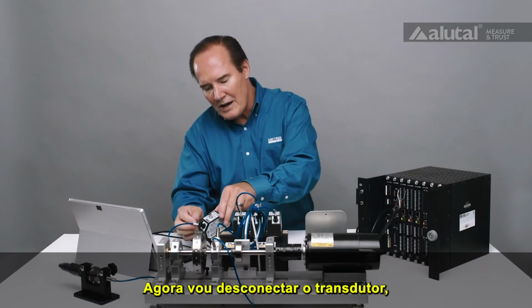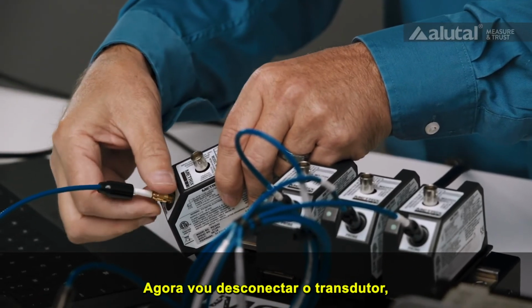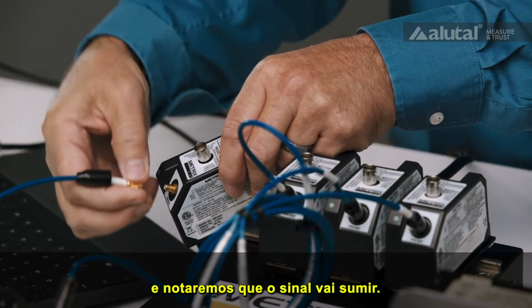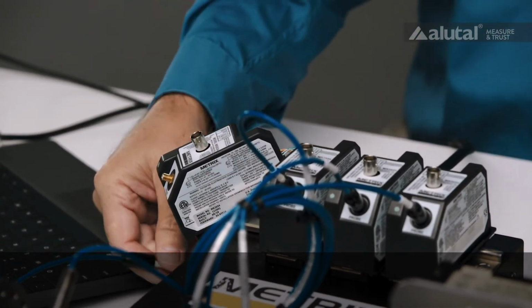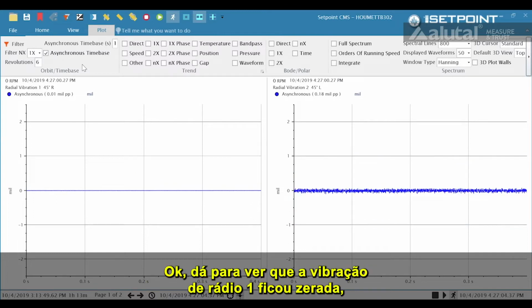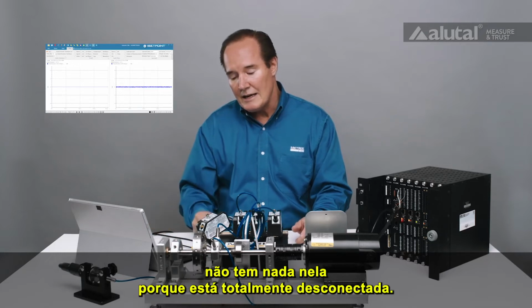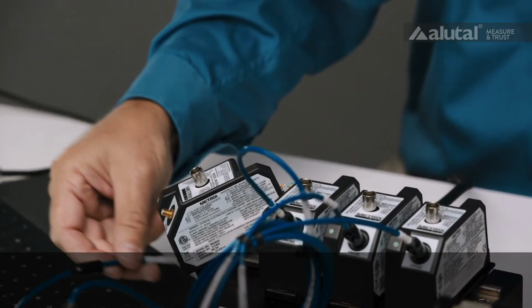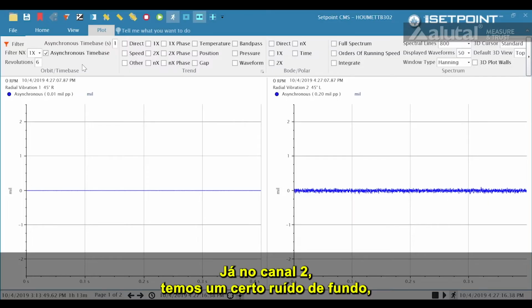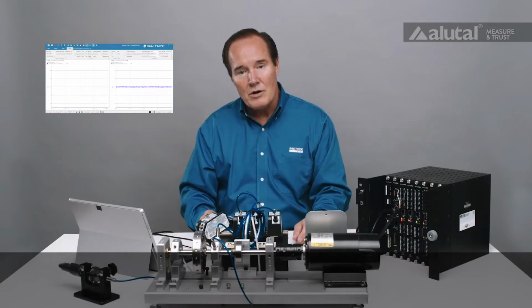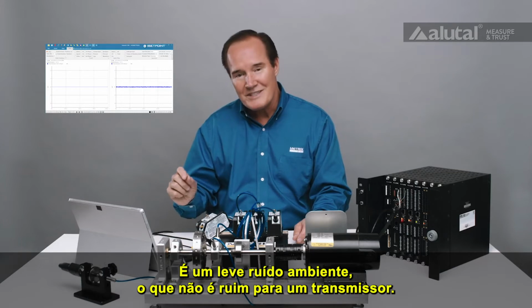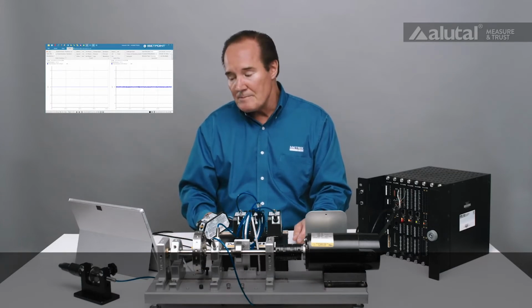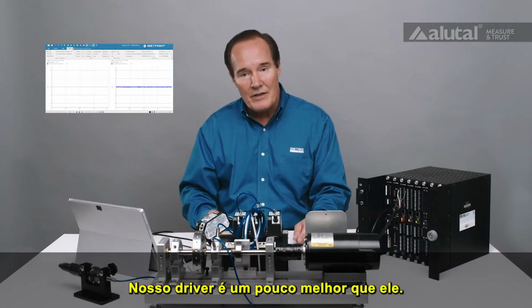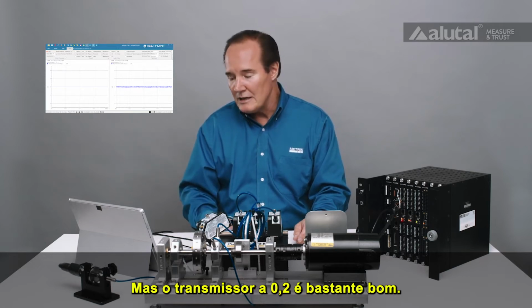So I'm going to disconnect this transducer, and what we'll see is that signal will go away. We'll update here in just a second. Okay, so you can see that radial vibration 1 went to absolutely 0. There's nothing on it, and that's because it's totally disconnected. And then you can see on channel 2, we've got a little bit of background noise, 0.2 mils peak to peak. So that's not bad. So what we have is a little ambient noise, and that's really not bad for a transmitter. Our driver does a little bit better than that, but for the transmitter, 0.2 is actually pretty good.